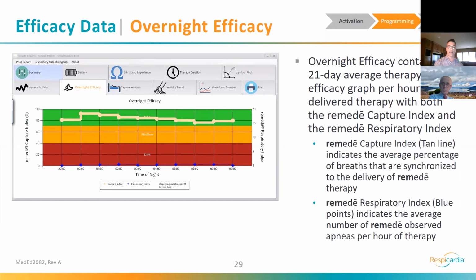And what we're highlighting here are any pauses of 10 seconds or larger, which may be indicative of a central apnea. This is an example of a well-titrated patient. We see our tan line at the top is in the green zone, which indicates a good level of entrainment. Generally 80% or higher of the breaths are as a result of our stimulation, and a very low index, hovering right around 0 to 1 throughout the night.